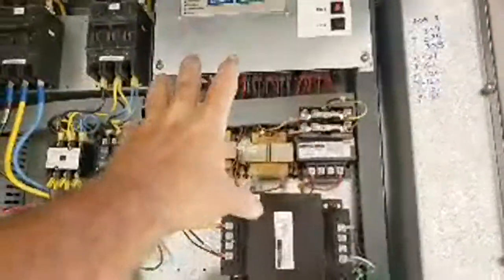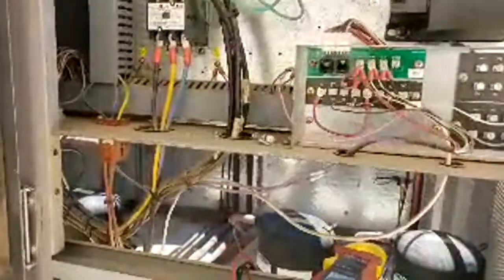Let's see. Just had a comment about an economizer wide open outside. Well, is it a control board controlling the economizer, or is it one of those little Honeywell W7212s or something like that, or one of the new Honeywell Jade controllers, which has a digital display? If you get one screw adjustment turned wrong on those, that'll cause the unit to stay open.